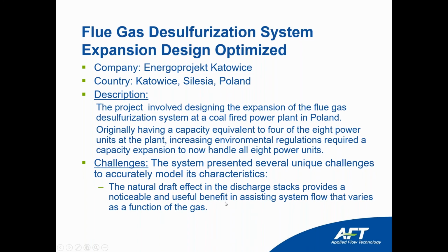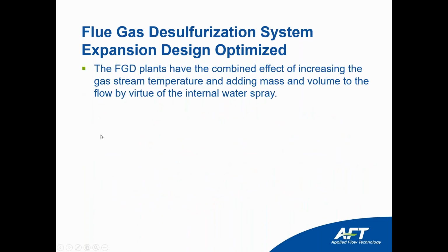The challenges. The system presented several unique challenges to accurately model its characteristics. The natural draft effect in the discharge stacks provides a noticeable and useful benefit in assisting the system flow, which varies as a function of the gas flow. This is the first challenge to model.